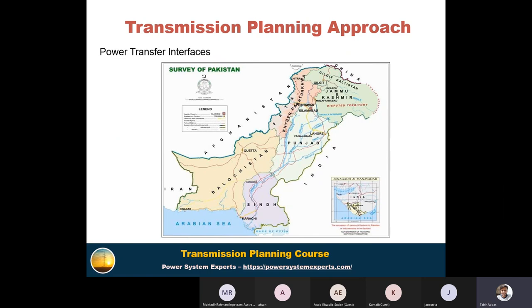So there are a lot of right of way constraints, because the northern part is a hilly and mountainous area, and the southern part is a congested area. So a lot of new technology is required to evacuate that generation from the generating station towards the load center. So in such a way, we perform a conceptual analysis. Basically, from the geographical point of view of the power sector, we see where power flows are coming from, where the power is coming towards the load center. Is there any right of way available, or should we move towards flexible AC transmission like FACTS devices? So all this information is related for a planner; these are the power transfer interfaces.